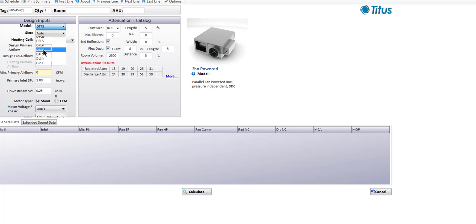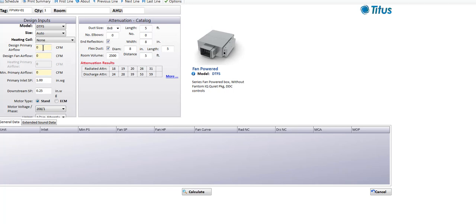Let's make a selection on a series fan-powered box — the DTFS, which is our commodity series fan-powered box. Let's say the design primary airflow is going to be 1,000 CFM. Sometimes people get into selection difficulties when trying to select fan boxes that are either too small or too big. I personally wouldn't put a fan box in the ceiling if the fan is only going to move 50 CFM — there's no point putting another blower and motor in. You'd be better off going with a single duct VAV box.